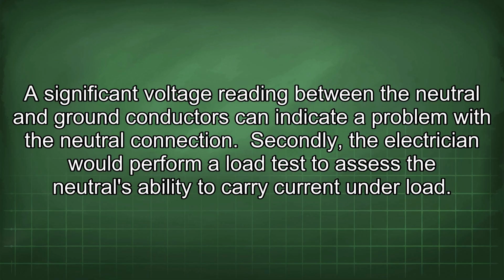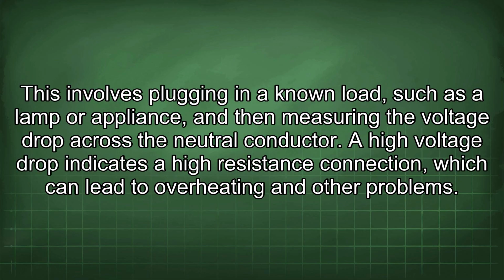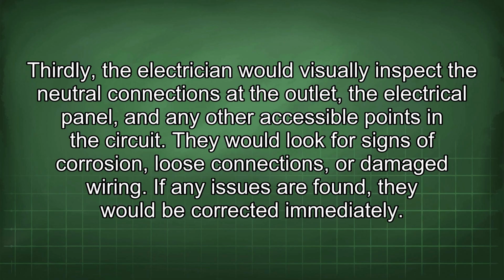Secondly, the electrician would perform a load test to assess the neutral's ability to carry current under load. This involves plugging in a known load, such as a lamp or appliance, and then measuring the voltage drop across the neutral conductor. A high voltage drop indicates a high resistance connection, which can lead to overheating and other problems. Thirdly, the electrician would visually inspect the neutral connections at the outlet, the electrical panel, and any other accessible points in the circuit. They would look for signs of corrosion, loose connections, or damaged wiring. If any issues are found, they would be corrected immediately.